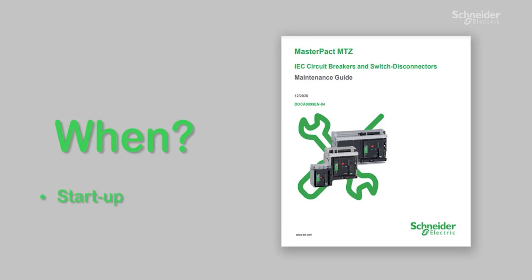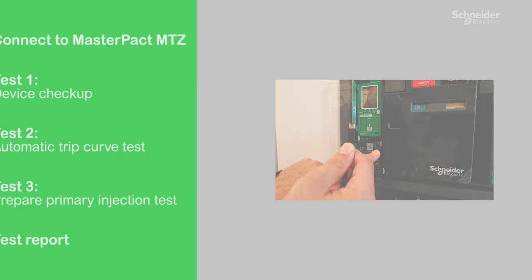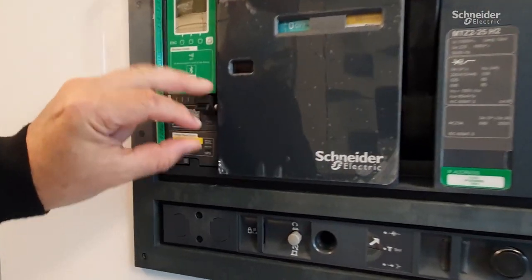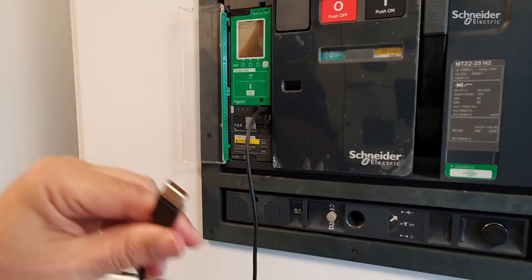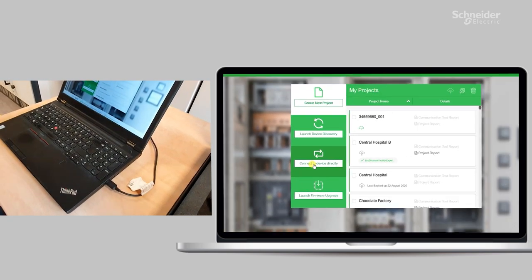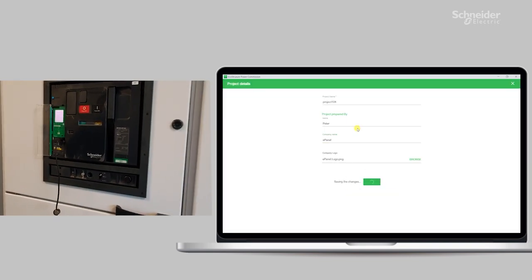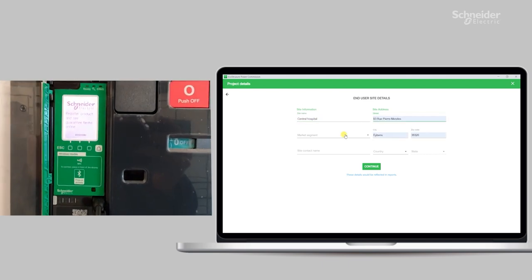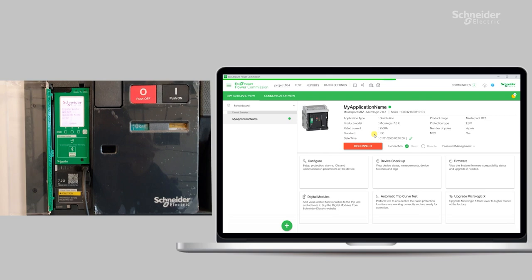Circuit breaker testing is recommended at both startup and every two to three years after that for preventive maintenance purposes. Launch EcoStruxure Power Commission and use the direct connection method. Just connect the laptop to the MicroLogic X on MasterPact MTZ with a mini USB cable, whichever way you add the MTZ to the EPC project. Ensure that you have selected the direct option in EPC and click on connect. This means you will have to connect your laptop and MTZ over USB even if the breaker has a remote communication module.